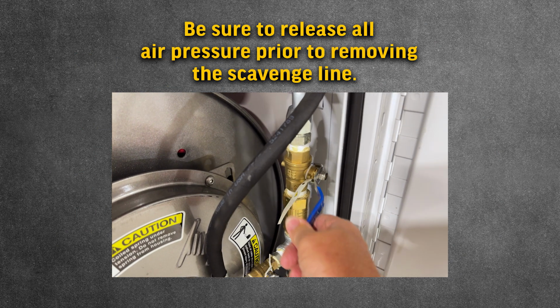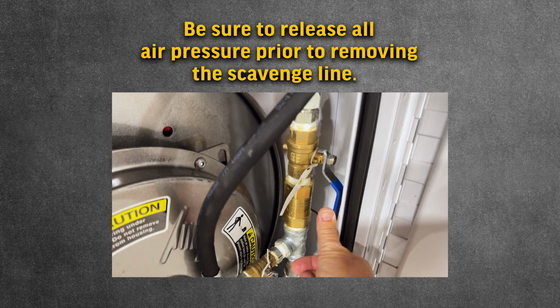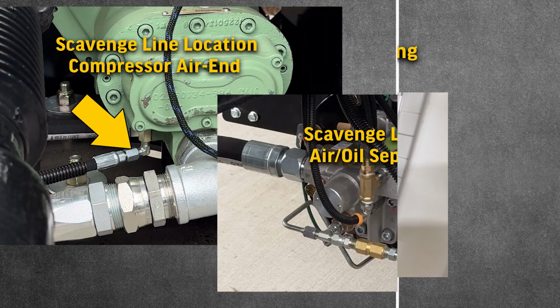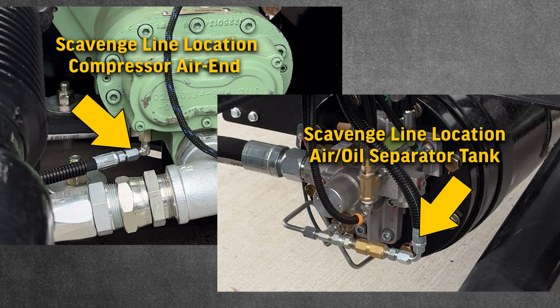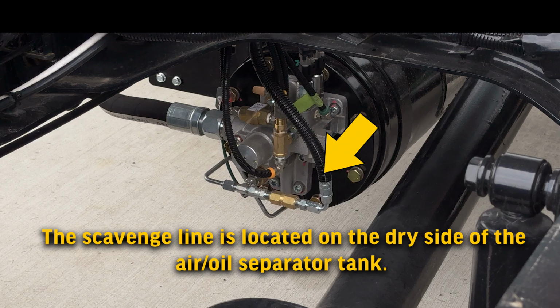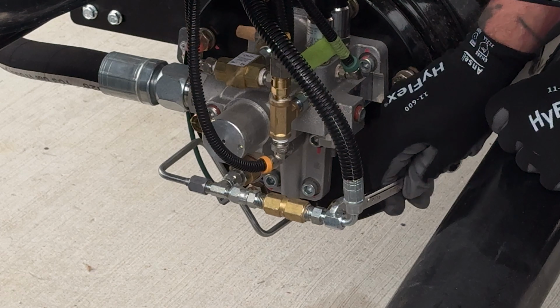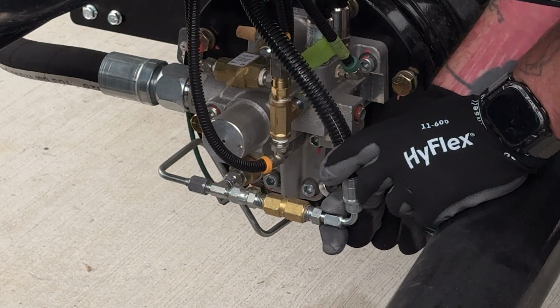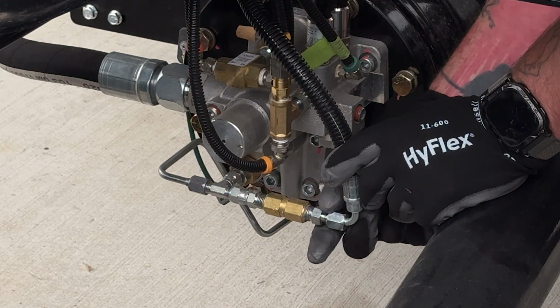Be sure to release all air pressure prior to removing the scavenge line. Let's begin by locating our scavenge line. The scavenge line is located on the dry side of the air oil separator tank. Using a 9/16 open-ended wrench, loosen and remove the scavenge line at the separator tank.